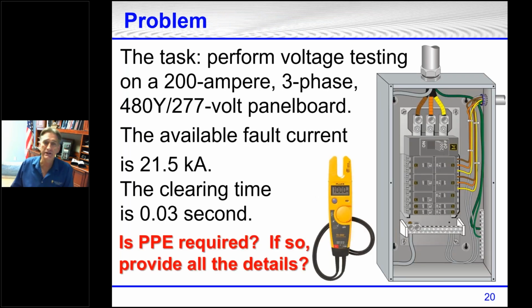So here's a problem, here's a task. Perform voltage testing on a 200 amp, 3-phase, 480Y/277 volt panel board. Now, if you notice, this panel board is Square M. You're probably familiar with Square D, and they are a really fine brand of equipment, but this is Square M. It is the Miller brand equipment. It is the Cadillac of equipment.